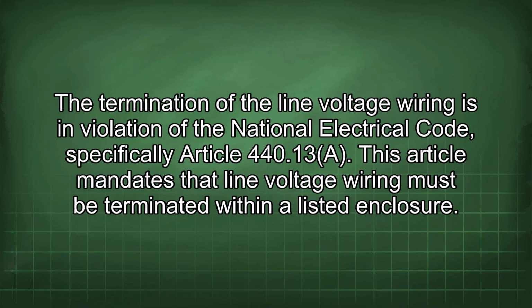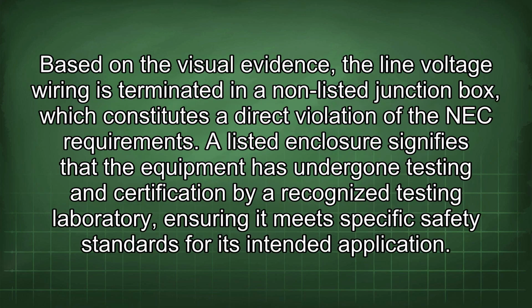Termination of the line voltage wiring is in violation of the National Electrical Code, specifically Article 440.13a. This article mandates that line voltage wiring must be terminated within a listed enclosure. Based on the visual evidence, the line voltage wiring is terminated in a non-listed junction box, which constitutes a direct violation of the NEC requirements.